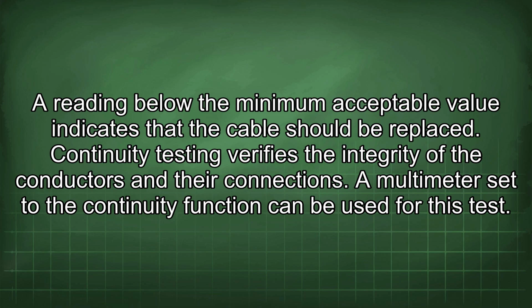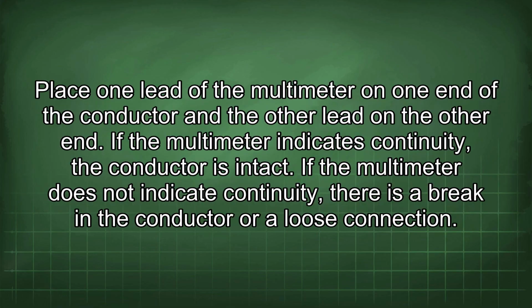Continuity testing verifies the integrity of the conductors and their connections. A multimeter set to the continuity function can be used for this test. Place one lead of the multimeter on one end of the conductor and the other lead on the other end. If the multimeter indicates continuity, the conductor is intact. If the multimeter does not indicate continuity, there is a break in the conductor or loose connection.